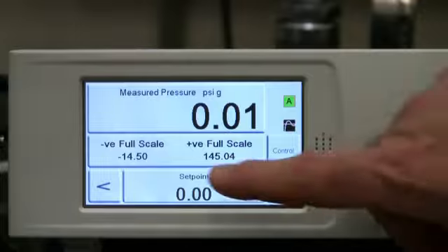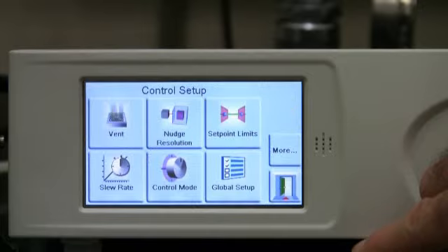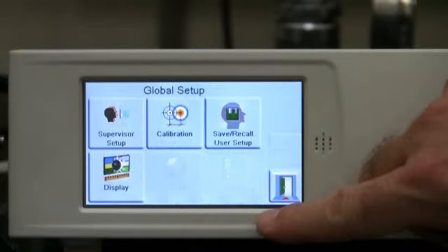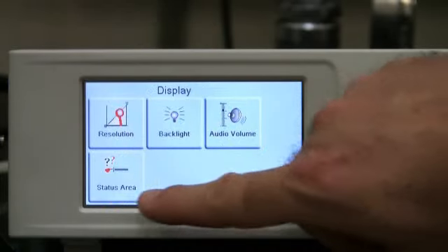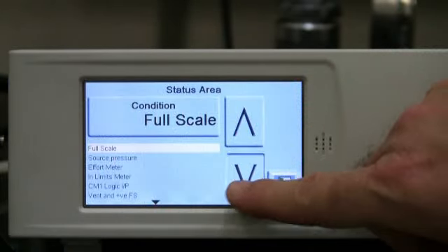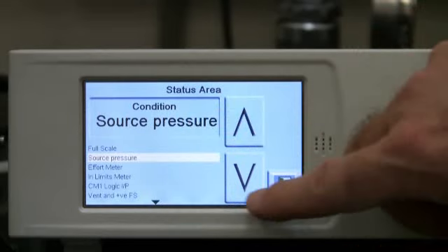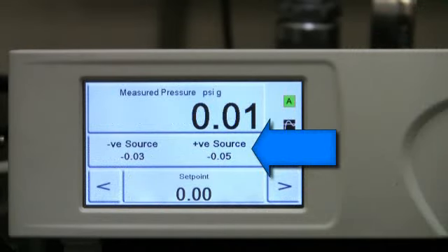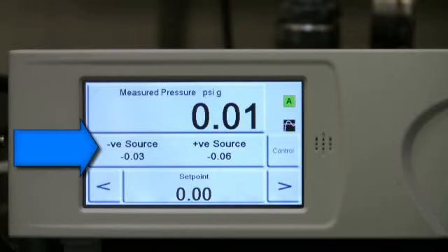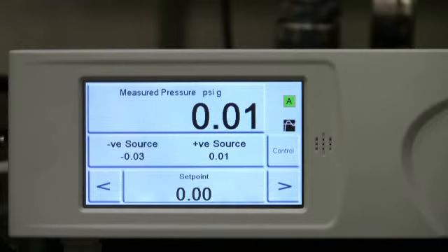In addition to the Druck piezo-resistive sensor, which provides a 1-year recalibration interval, reducing cost of ownership, PACE5000 also includes sensors that monitor the source pressure and vacuum. We can change the center section of the display to indicate this information on the main menu, allowing the user to easily confirm the correct source pressure is applied.